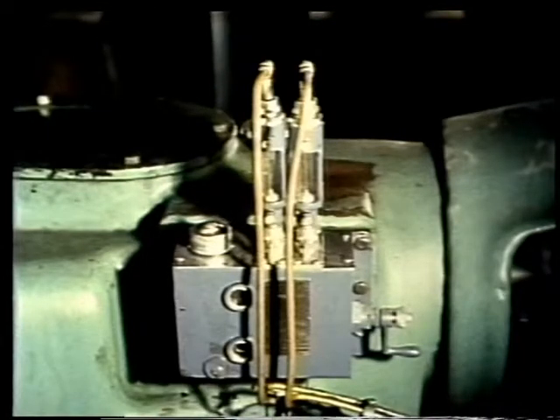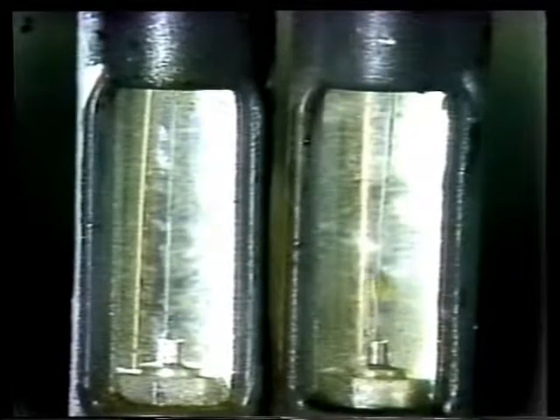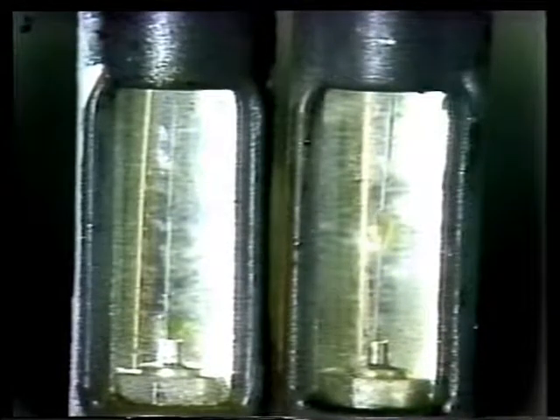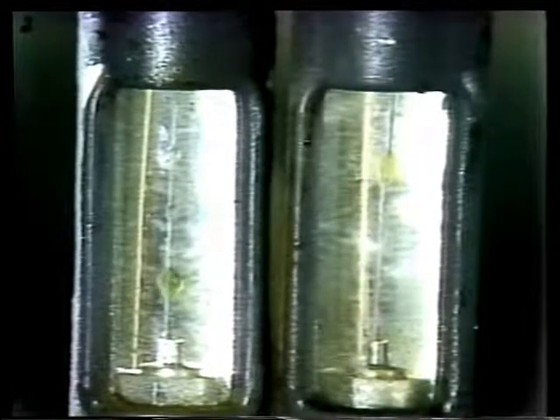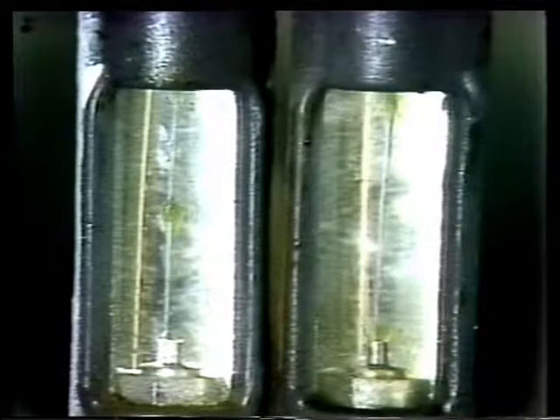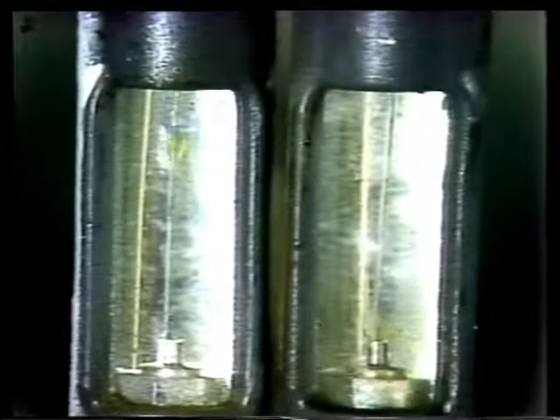On many compressors, lube oil is also delivered to the cylinders through an oil pump and a lubricator. To keep a cylinder lubricated, oil has to be supplied at a certain rate. On this compressor, you check the rate by watching oil drops flow up a guide wire in a sight glass. The manufacturer's manual will tell you how many drops per minute.